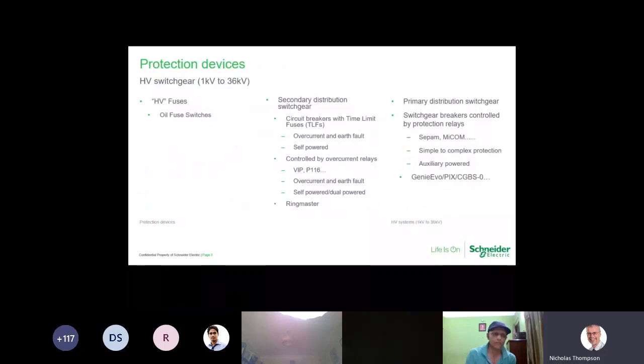So when we start to look at our protection devices, we've got three main areas. We've got traditional fuses. These are the HV fuses, which came in various different sizes. That was the traditional form of protection for distribution transformers up to about 30 years ago. Then we moved into two classifications of equipment called primary and secondary distribution switchgear. When we start to look at the two types of equipment, they've both got very different requirements.